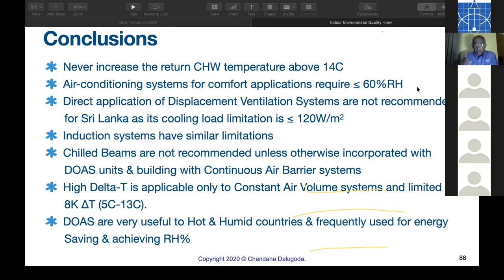Normal air conditioning, we don't have RH meters, controllers, okay, uncontrolled. So you have to design the plant has to be below 60, that is ASHRAE 55. Now I have seen it is going slightly up, but it's a humid country, has to be below 60. For my opinion, you target 55 RH.